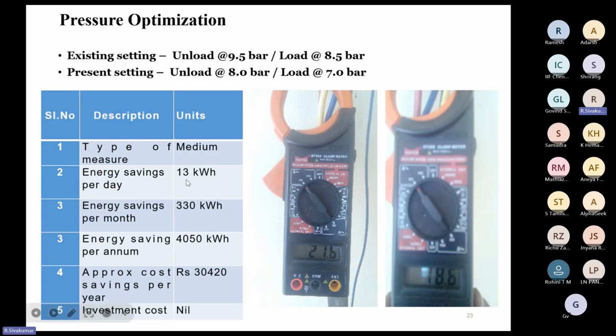Previously, you see the clamp meter reading: earlier it takes 21.6 amps. This is the 11 kilowatt, 15 HP screw compressor. With the same compressor and the new pressure band, maximum 8 bar setting, it takes only 18.6 amps. So 3 amps of current consumption is reduced. The company operates for only 12 hours, so 13 units were saved in a day, and almost 4,050 units a year.